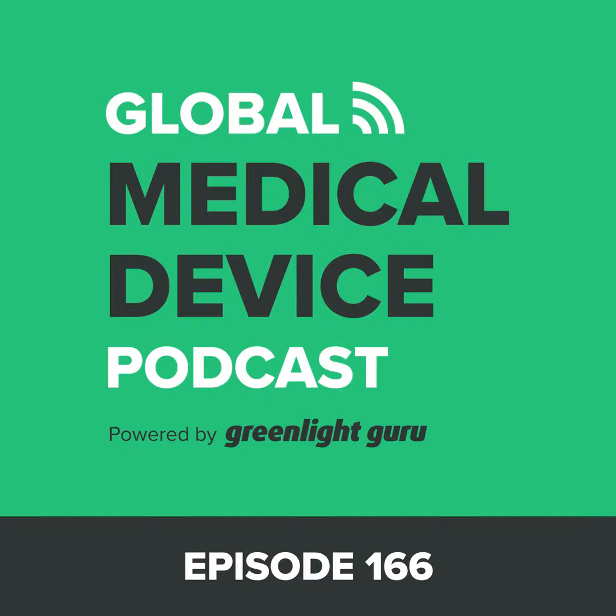First of all, because as you know very well, Jon, ISO 14971 says quite clearly, it's one of the things that I agree with them on, that labeling should not be a primary risk mitigation measure. In other words, we should always do everything else that we can based on design, based on training, yada, yada. And labeling should be a last resort.